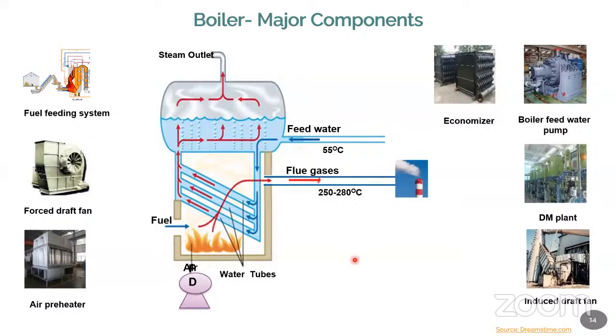So in a boiler, we can tell n number of energy conservation proposals like this. And the third important point: you can take the flue gas and filter it, because sometimes some ash will also come out. You can't directly use the flue gas for your application, so you can filter out the ash. Now that air is hot. If you pass it on to the fuel, particularly wood, what will happen? The moisture content will be removed. So that can again be used as fuel for the chamber. When the moisture content is removed, it will quickly burn and reach the temperature, and that will also save energy.